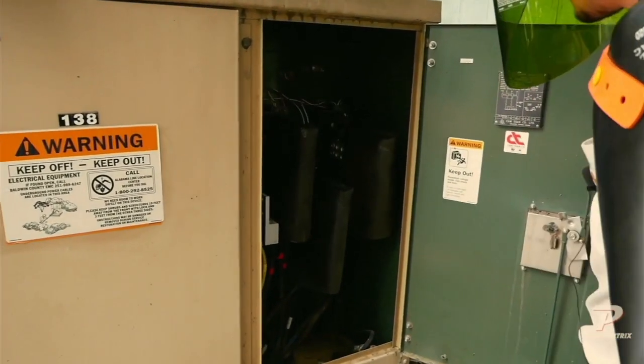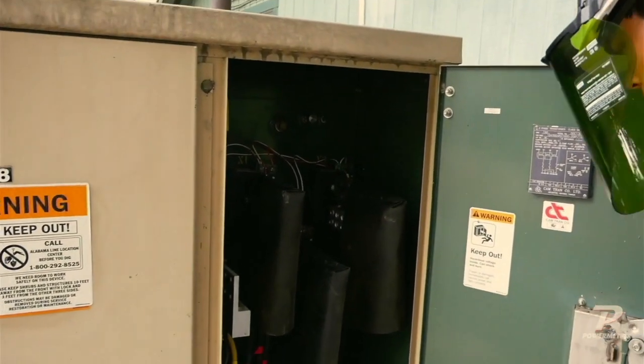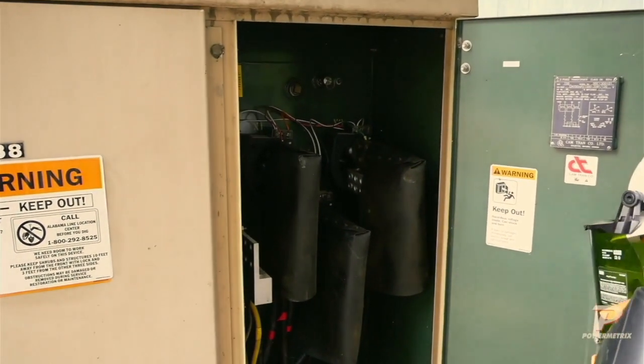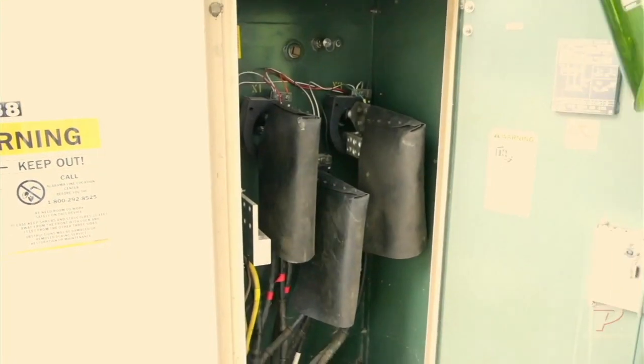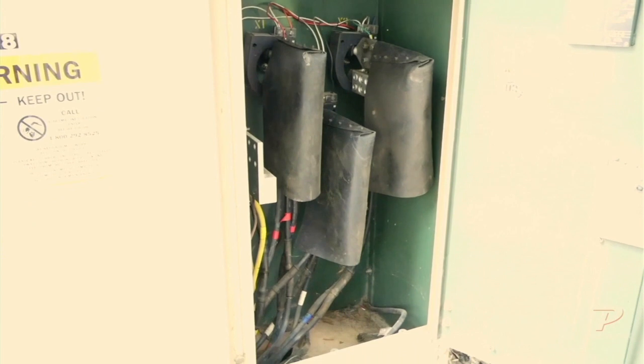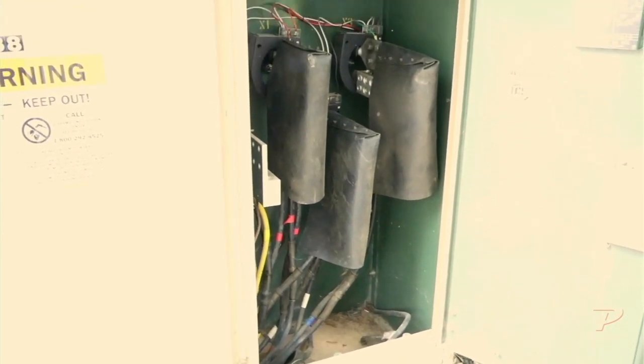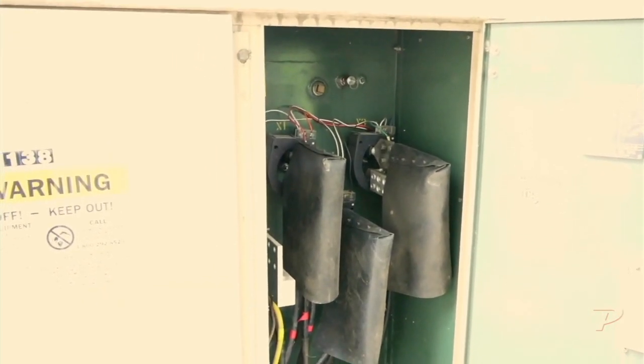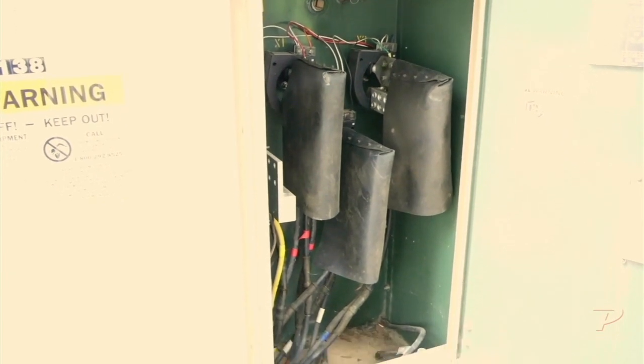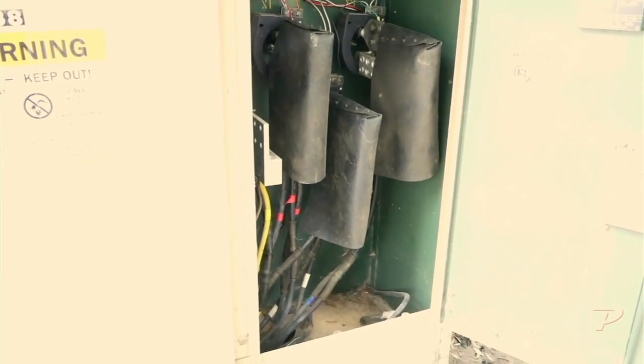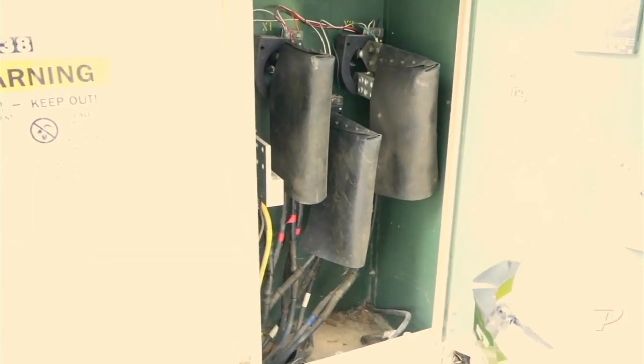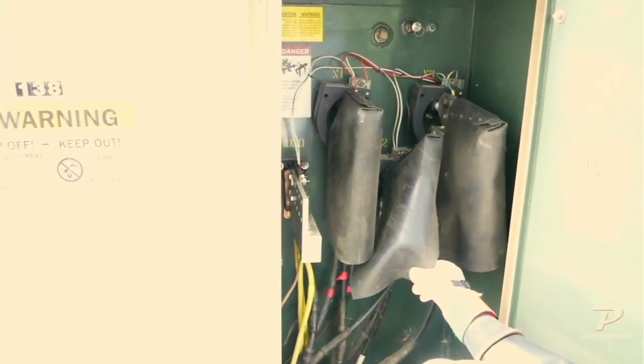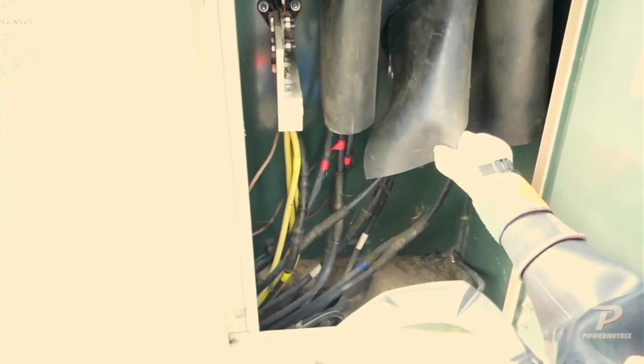At this point, you saw on the inside of that meter, you might just do a quick confirmation: they said out there that the multiplier was 40. Are you confirming that inside there? Yes, you're seeing they're 200 to 5 CTs. So them saying 200, and you seeing 200 to 5 CTs confirms what we saw on the meter. So while you're there, just do a quick check, because someone could have mislabeled something.